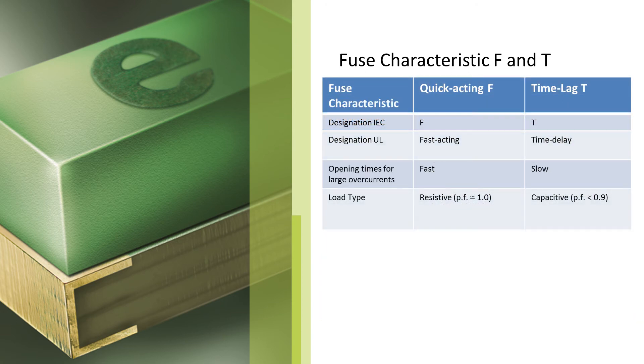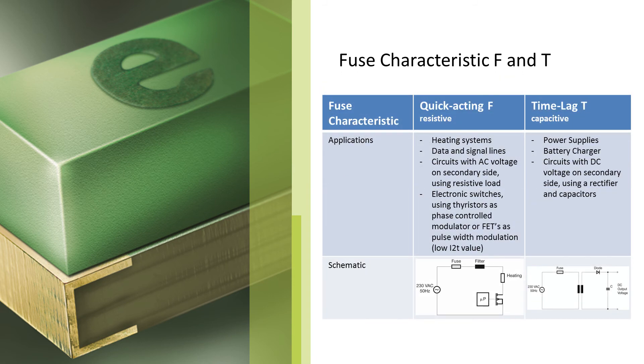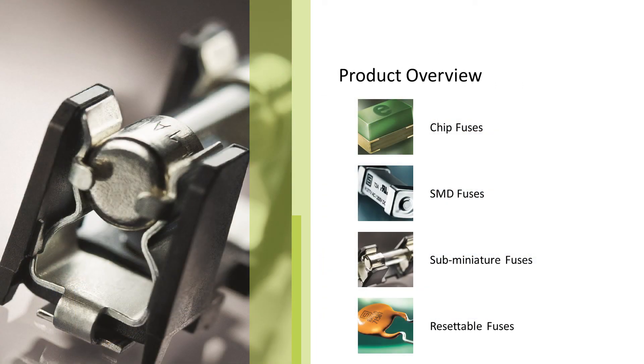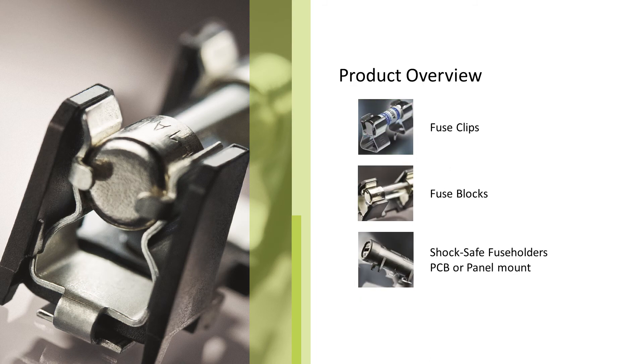Time-lag fuses interrupt slower than quick-acting fuses. They are more robust to survive high inrush current peaks, and are often used for capacitive load types with such inrush current peaks. Typical applications are power supplies, battery chargers, and primary circuits with rectifiers and capacitors. Schurter offers a broad range of fuses and fuse holders catering to different needs.